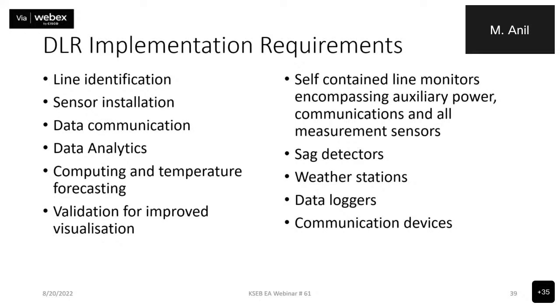One UK-based firm has come up with communication equipment through fiber optic cable without any power requirement for monitoring these conditions at site, so that without any auxiliary power we can achieve transmission of whatever data is required from the field to the system operator. Presently they say they have a 30 kilometer distance range for the system to operate without auxiliary power at the remote end, between the remote end and the system operator point.